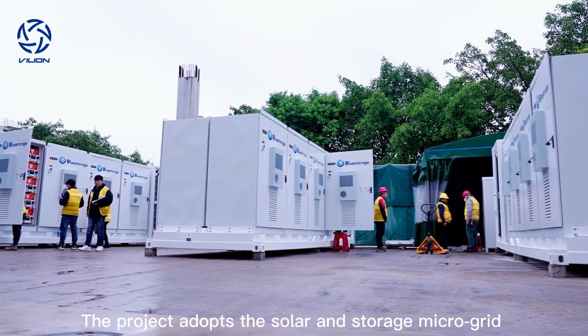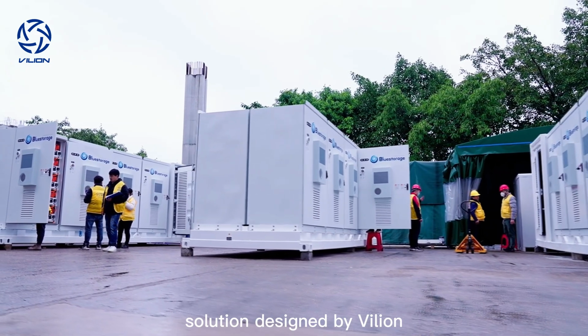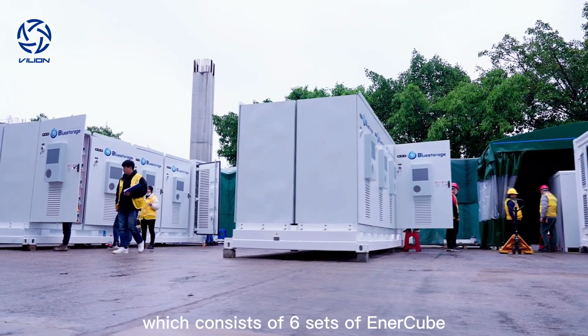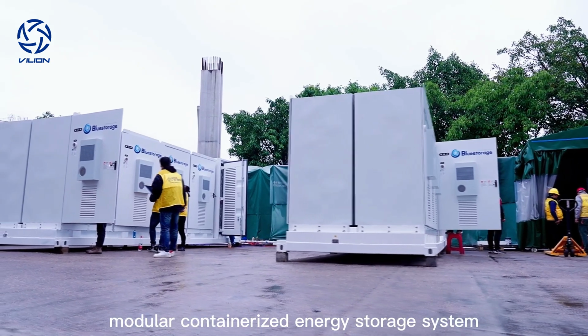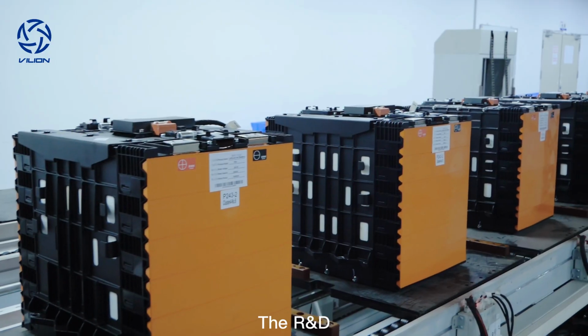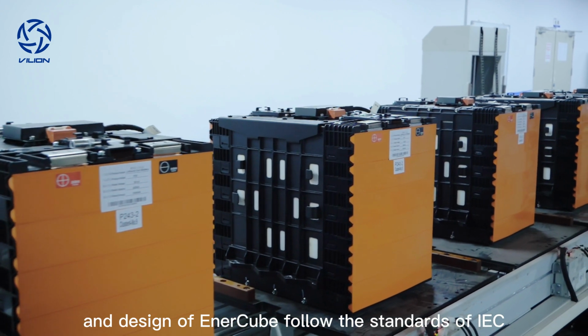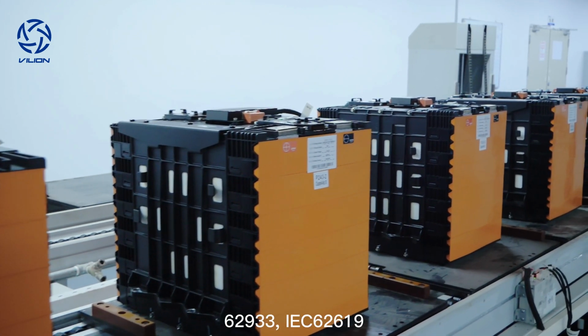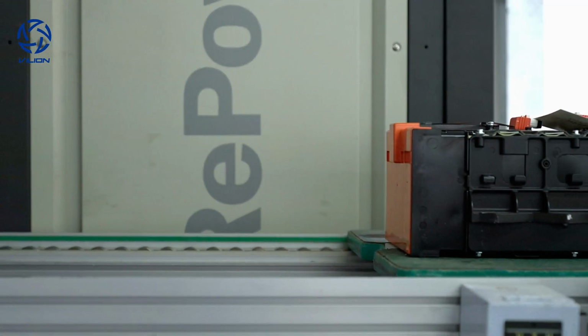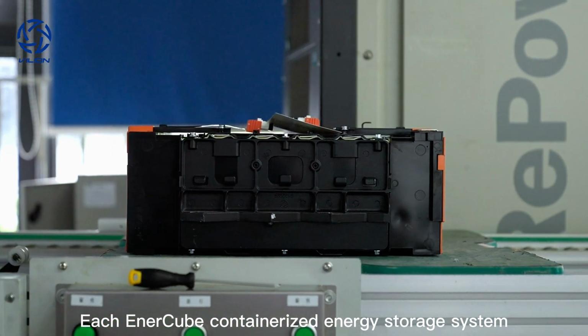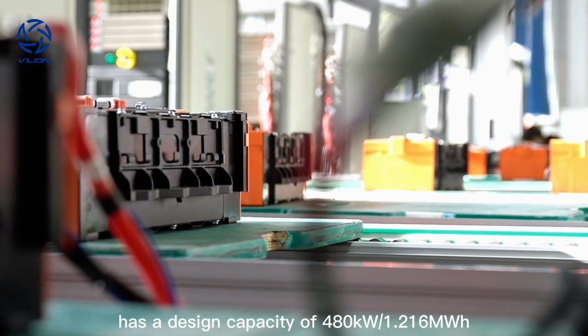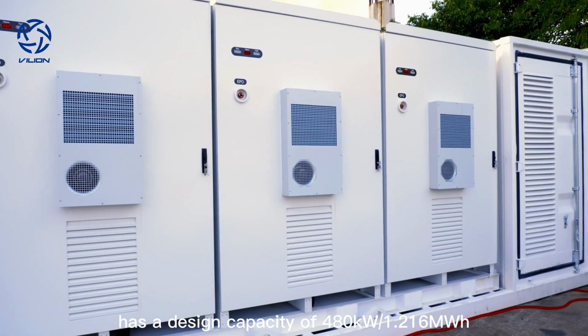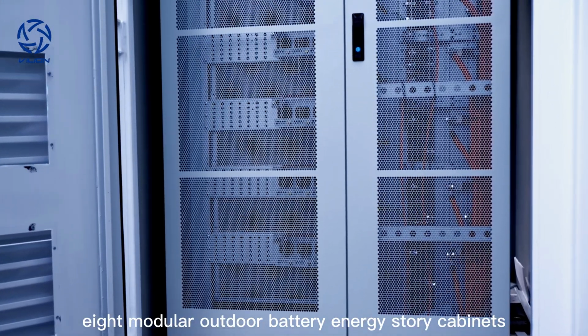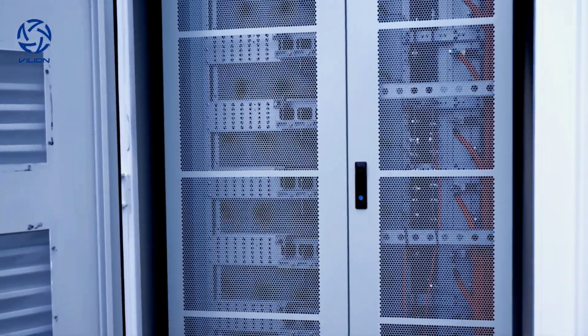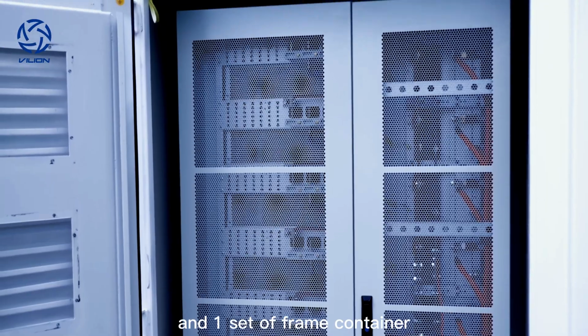The project adopts the solar and storage microgrid solution designed by Vilion, which consists of 6 sets of N-Cube, the third generation modular containerized energy storage system. The R&D and design of NQ follow the standards of IEC 62933, IEC 62619, UL9540, etc. Each N-cube containerized energy storage system has a design capacity of 480 kW, 1.216 MWh, including 8 modular outdoor battery energy storage cabinets, 1 independent electrical room, and 1 set of frame container.